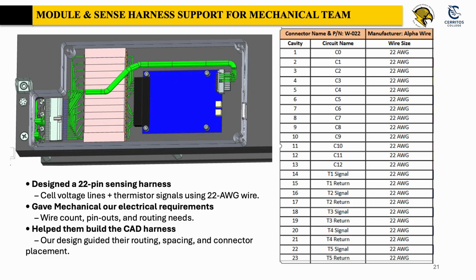Pins 14 through 23 are all temperature sensor circuits. Each temperature node has a signal and a return path, so the BPCM can accurately capture thermal behavior across the module. Everything here uses 22 AWG alpha wire, which meets the voltage insulation and current requirements for low voltage sensing. This sizing also matches what the BMS OEMs typically expect, so it keeps us compliant and easy to integrate later.